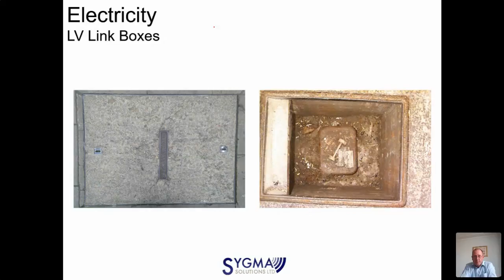I was doing a basic cat engineering course in Birmingham years ago, and a surveying company had been along, and we went out to site to do the practical bit, and there was a double link box, which you can always tell because there's 2 lids side by side. On the survey drawings, they had 1 cable in and 1 cable out. That would imply to me that they didn't have the original plans. I said to the guys straight away, you've got to be very, very careful here, because that's a double link box - that means you've probably got 4 in, 4 out. Without plans, it's hard to tell, which goes back to the obvious necessity of always having plans.